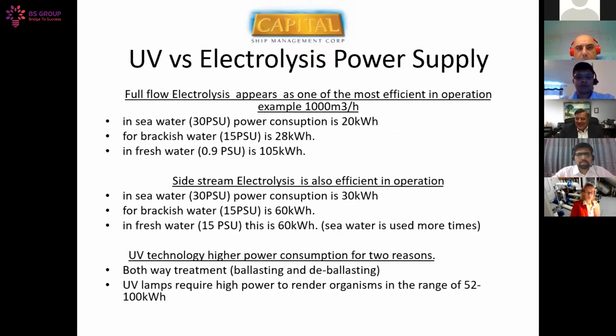Now, a bit comparing UV versus electrolysis power supply for a system of 1,000 cubic meters per hour. For a PSU of 30, there are quoted consumptions of 20 kilowatt hours, going up to 100-105 for freshwater operation. For side streaming, the figures are not significantly higher, but of course there is a limitation of PSU. For some side streaming, PSU is up to 15.